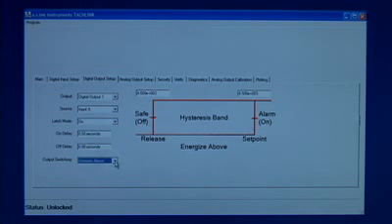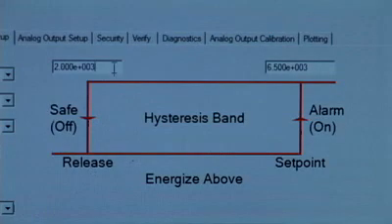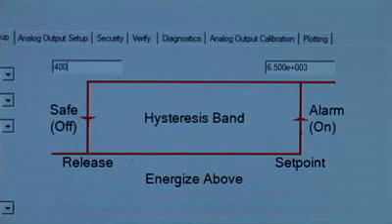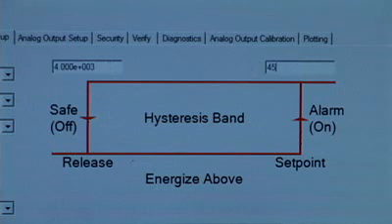Tab to output switching and select ENERGIZE above. Move cursor to SAFE and set to 4000. Move to ALARM and set to 4500.